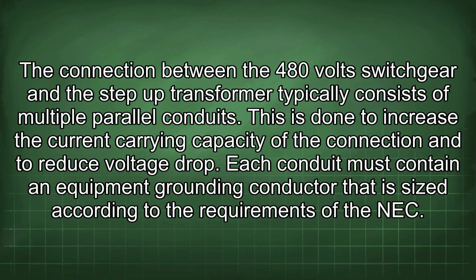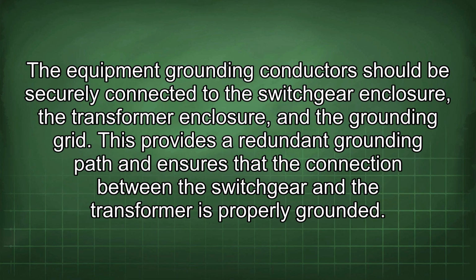A connection between the 480-volt switchgear and the step-up transformer typically consists of multiple parallel conduits. This is done to increase the current carrying capacity of the connection and to reduce voltage drop. Each conduit must contain an equipment grounding conductor that is sized according to the requirements of the NEC. The equipment grounding conductors should be securely connected to the switchgear enclosure, the transformer enclosure, and the grounding grid. This provides a redundant grounding path and ensures that the connection between the switchgear and the transformer is properly grounded.